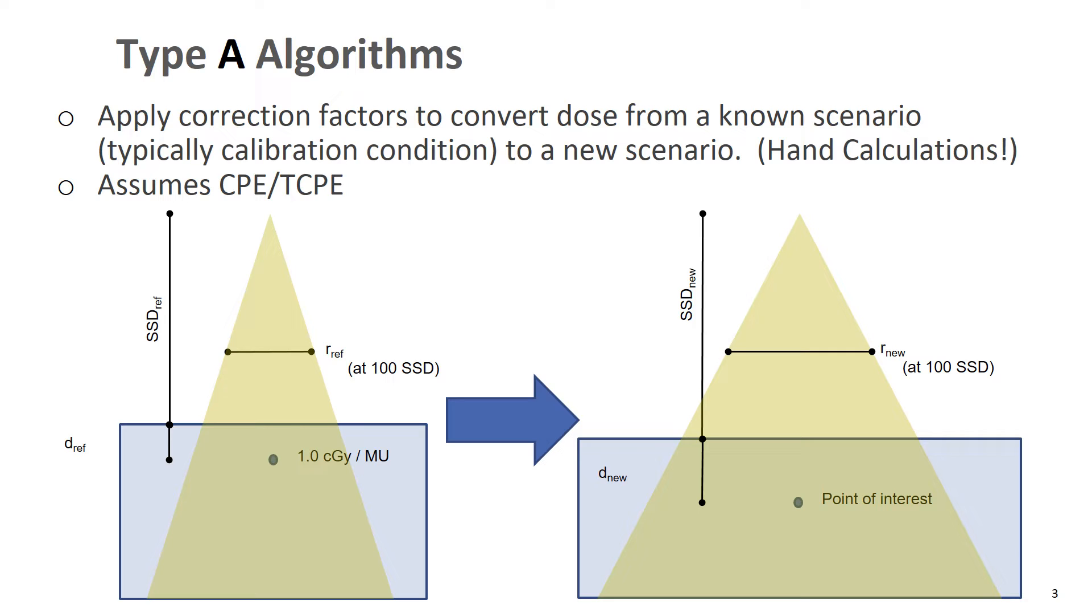And so we want to convert dose from the situation on the left where we know what the dose is to this new situation on the right. And we can use a series of empirically measured correction factors, whether that's a scatter factor, or an inverse square correction for distance from the isocenter, or a percent depth dose curve, or a tissue maximum ratio curve, or a wedge factor if we've got a wedge or a tray placed in the beam. We have these empirically measured correction factors that we can use to convert the dose from the situation on the left to the situation on the right.